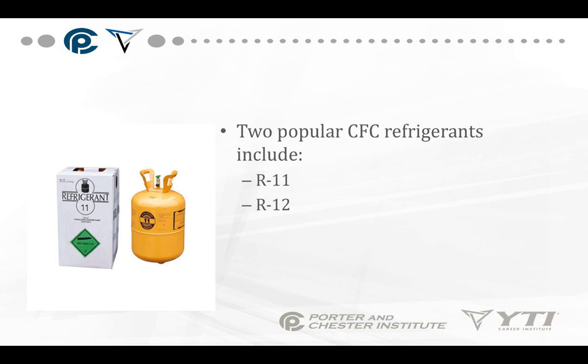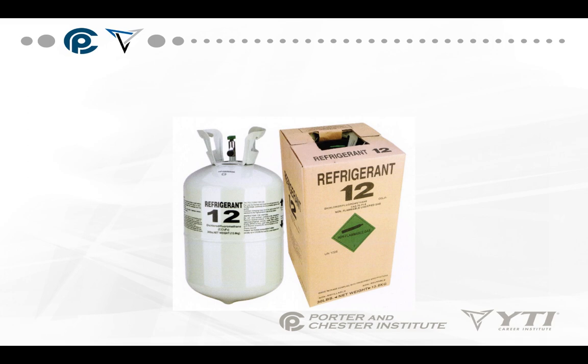The key word we have to be really worried about is chlorine. Chlorine is extremely bad for the environment when in the air. Two popular CFC refrigerants include R11 and R12. You will not find these on the market any longer. If you find them, be very suspicious of them — they're extremely expensive because they can no longer be manufactured. Any R12 that's available has either been recovered, reclaimed, or brought over the border from Mexico.